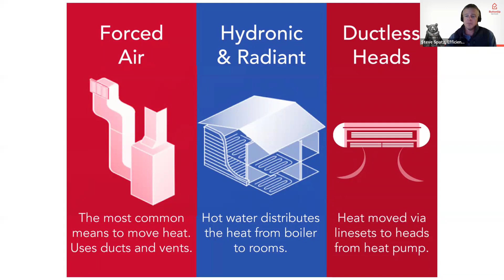And then manufacturers also have the same type of ductless wall mount heads that Bob showed you with the ductless equipment. The difference there is that you're running hot water through the coil in that ductless unit on the wall rather than hot refrigerant. And in this situation too, with an air-to-water system, that heat pump can chill the water in that storage tank as well. So with a ductless head or a forced air system in a building using an air-to-water heat pump, you can do both heating and cooling with that type of equipment. But most predominantly what we're seeing is an air-to-water heat pump in a hydronic heating system with traditional types of hydronic distribution through the home.